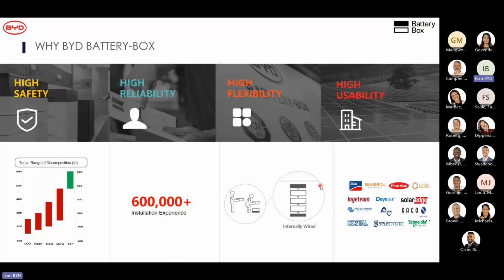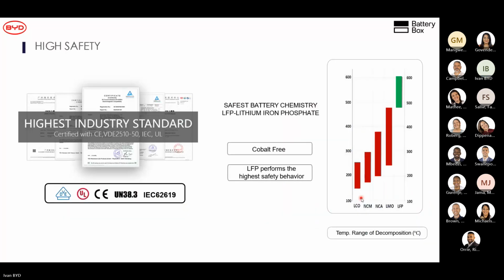In terms of the tower designs, they're internally wired, which means it's basically electrical Lego, and quite often it takes longer to unpack the batteries from their box than it does to make a tower. And here's our compatible inverters, but we'll touch more on that later. Here's some of the summaries of those safety devices. Even when the batteries get that high, there's nothing flammable in the battery to catch fire. So these are really quite safe batteries, with all the certifications, which makes shipping them around the world very easy.